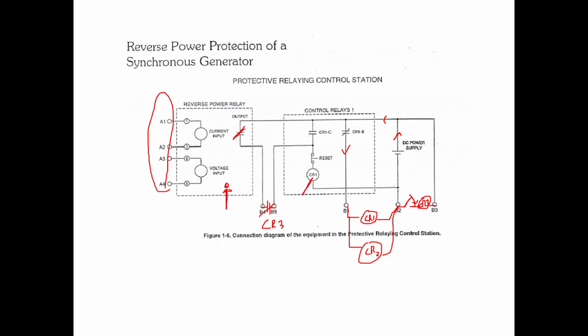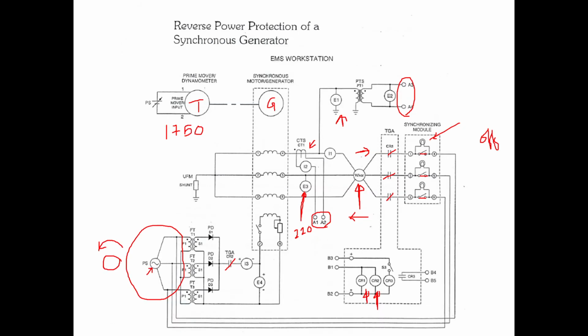Here the CR1 coil will energize. When the CR1 coil energizes, this contact will close for holding and this contact will open. When this contact opens, CR1 and CR2 will de-energize. When CR1 and CR2 de-energize, these closed contacts will become open. So now we have isolated the generator from the grid. When you disconnect CR1, you isolate the generator from the grid, and you are also opening the contact here so that the current in the excitation is also zero. So this is how the circuit works.